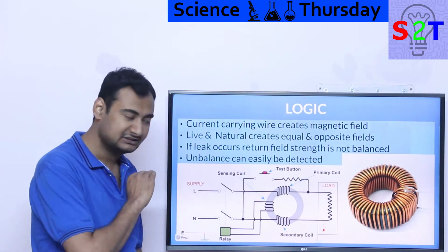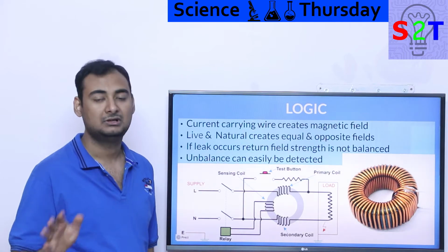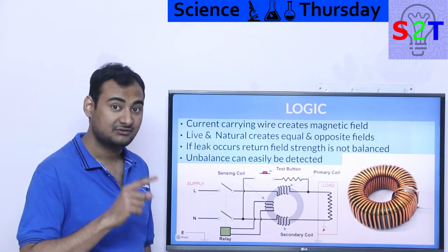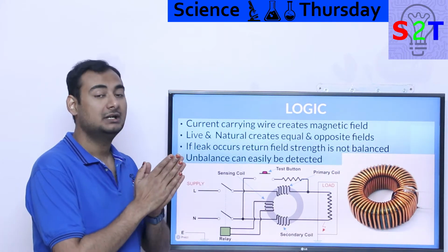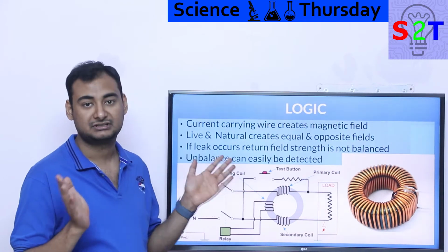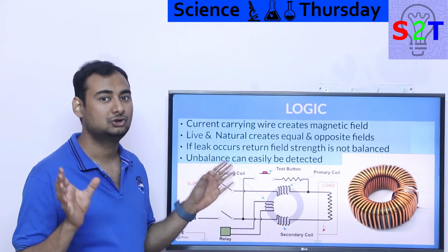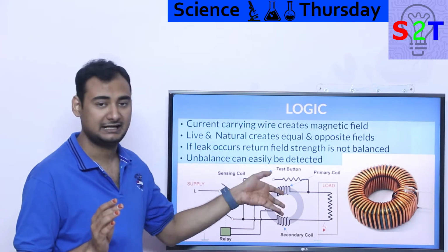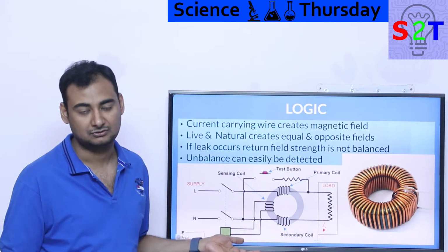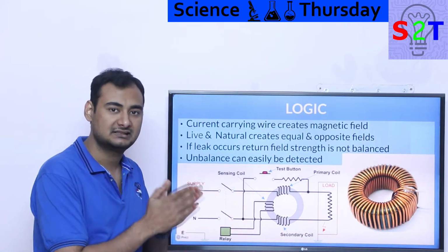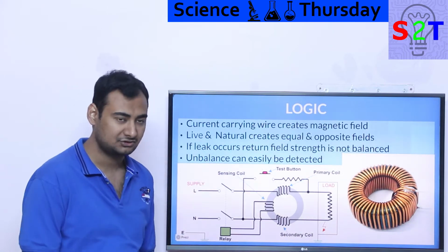Be very mindful. It does not do anything about overload, over-ampere draw. That's why we still have an MCB. Sometimes MCB and earth fault protection can be merged into one device, but generally they are two separate devices, and you cannot say, hey, I have ground fault protection, so I'm safe from overcurrent. No, all you are safe from is ground leakage. So that's the logic behind it.